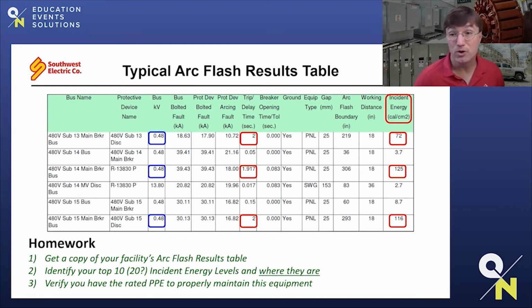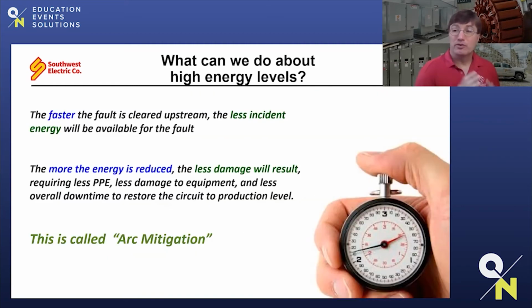So here's what I'd like you to do knowing this. I'd like you to go to your facility management or your maintenance department and see if you can get a hold of a copy of the arc flash assessment. Look at the arc results table. Where are the highest incident energy levels in your facility? What equipment is that? Can you locate that equipment? And then double check, does your facility have the proper PPE to handle these energy levels? Or do they have rules in place to not work on this equipment live at all? So these are the two critical areas in every arc flash assessment.